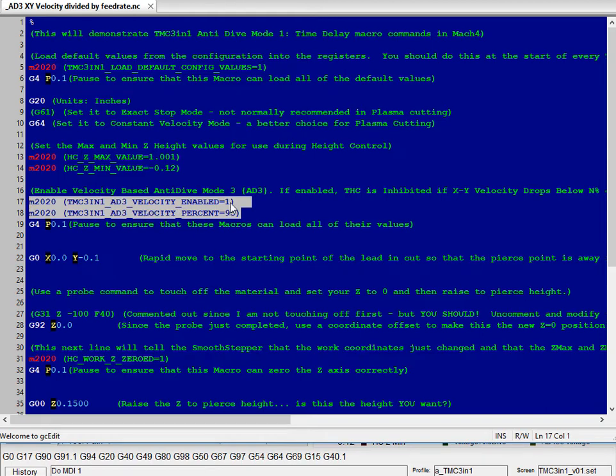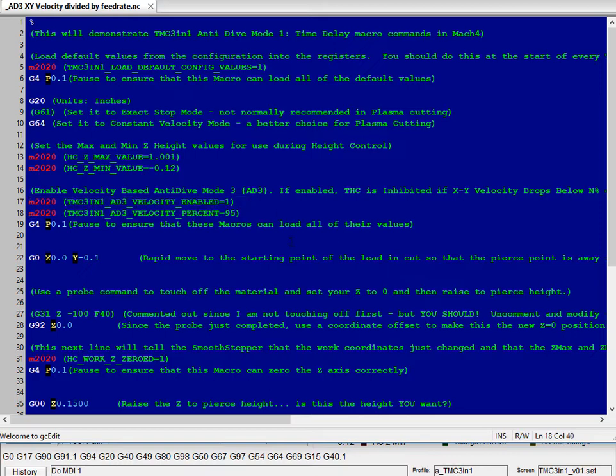Here are the interesting lines. AD3 velocity enabled equal to 1, so we're enabling anti-dive mode 3, and we're setting it to 95%. So if you're commanding 100 inches per minute and you're doing 95 inches per minute up to 100, height control will be enabled, which would be during the middle of your long lines. If you drop below 95% of your commanded feed rate, which would be at the very beginning and very end of your line, height control will be disabled.